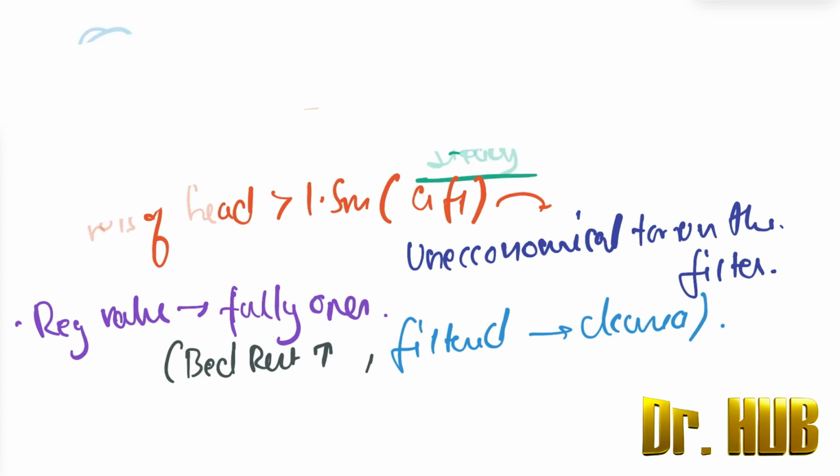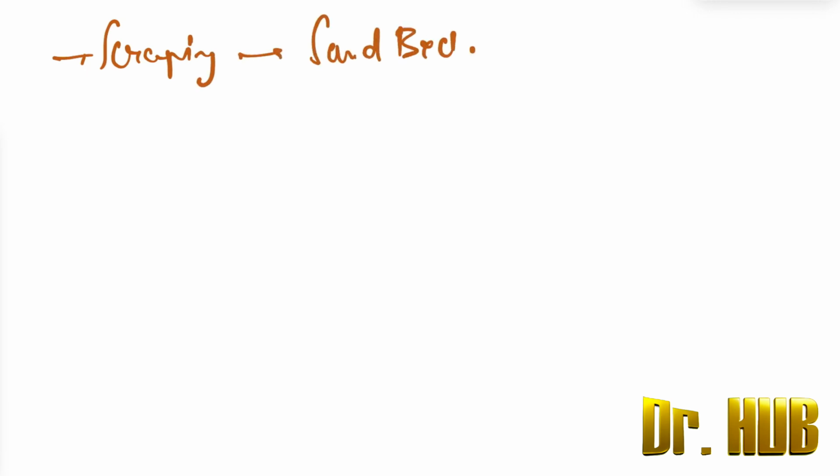So how is this cleaning done? It is done by scraping the sand bed, which does not need to be done by skilled labor. After several years of operation, that is about 20 to 30 scrapings, the sand bed can be changed as it will diminish in size.